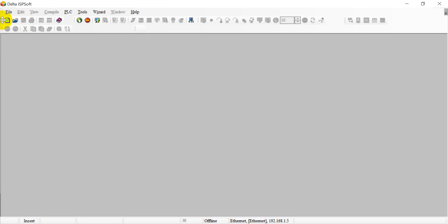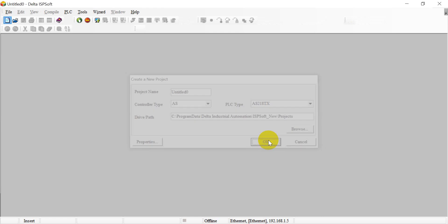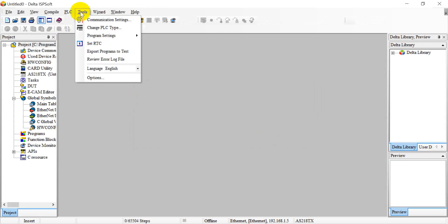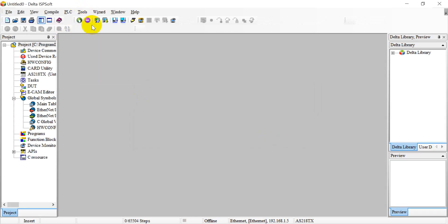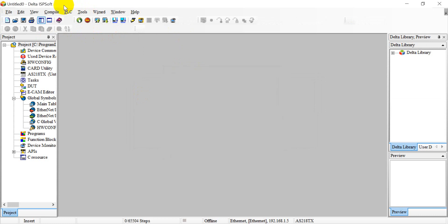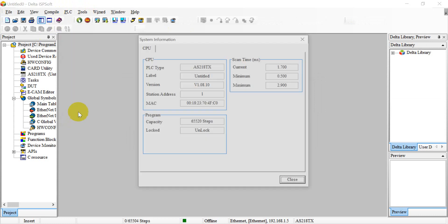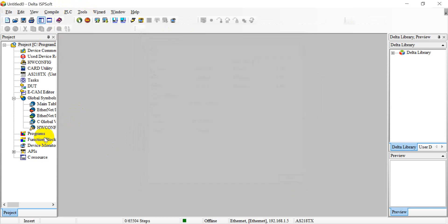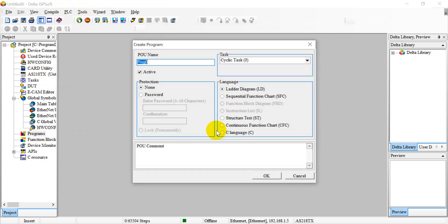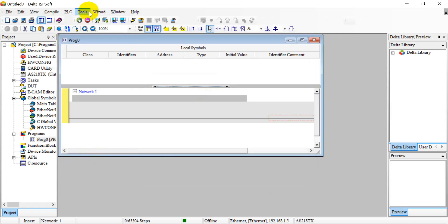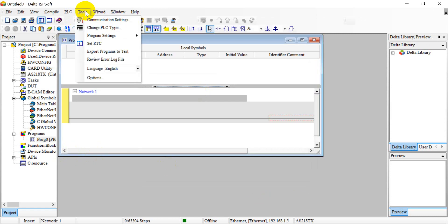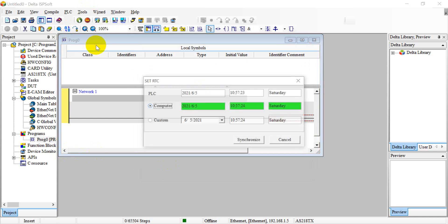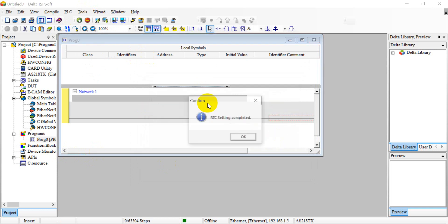First we will create a PLC. Then select tool, communication setting. After that, check the connection status, then we must create a POU. After that, please remember to set the real time clock, because AS PLC don't provide a battery inside, so please make sure to synchronize the time.